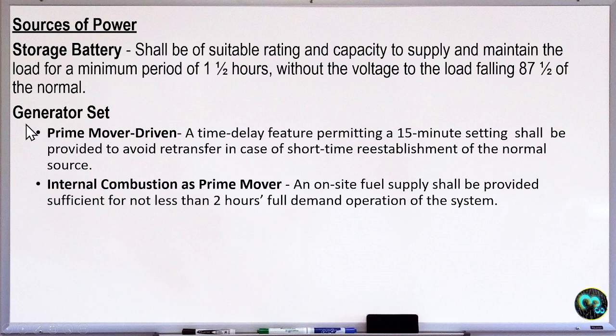So if you're using a generator set, prime mover driven, the time delay feature should permit 15 minutes setting and shall be provided to avoid retransfer in case of short-time reestablishment of the normal source. So it should not transfer immediately in case of an abrupt loss of our normal load. There should be a time delay, so the prime mover could be set with a time delay. Internal combustion engine as prime mover and on-site fuel supply shall be provided. The fuel shall be sufficient for not less than 2 hours of full operation.